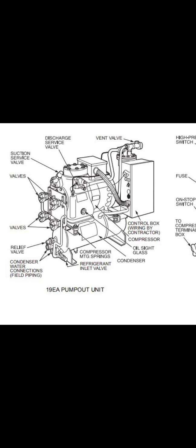And because of this risk, suppose in the plant room any big leak comes, or a serious leak comes, and the air will cut off. The company provides breathing apparatus with fresh air for emergencies. If the plant has any big leak, we can wear this fresh air, oxygen breathing apparatus and go to the plant room for the emergency. It's a very big plant. Therefore I will be talking about larger plants and handling huge quantities of refrigerant.